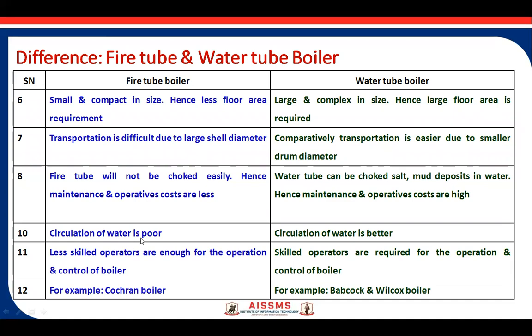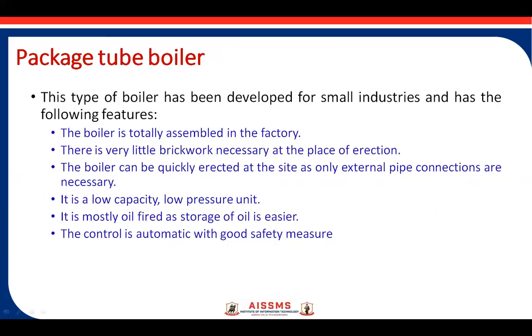Circulation of water in fire tube boilers is generally natural and therefore poor, whereas in water tube boilers pumps are used along with better tube arrangement, resulting in better water circulation. Less skilled workers are required to control and operate fire tube boilers. Examples of fire tube boilers include the Cochran boiler, and examples of water tube boilers include the Babcock Wilcox boiler.